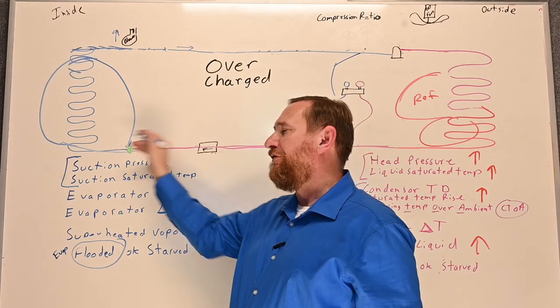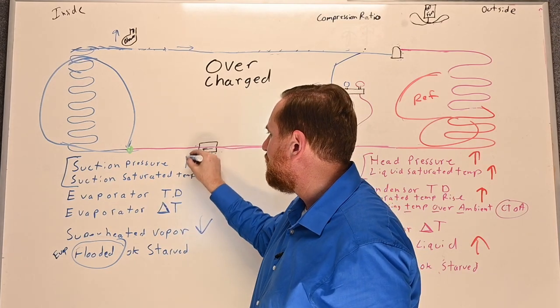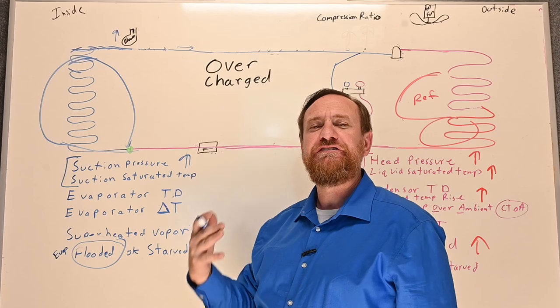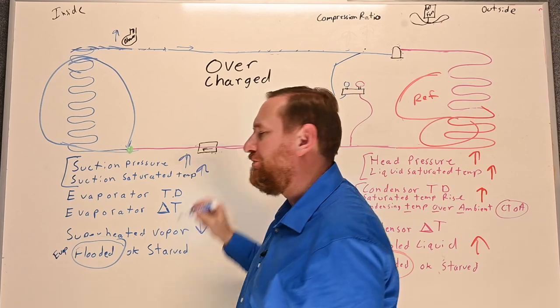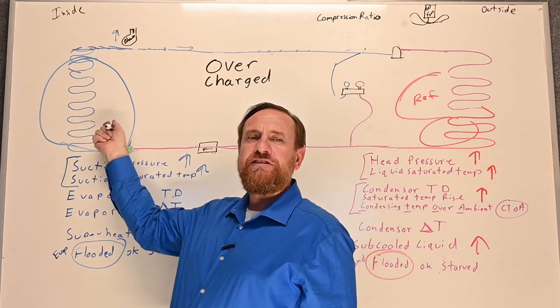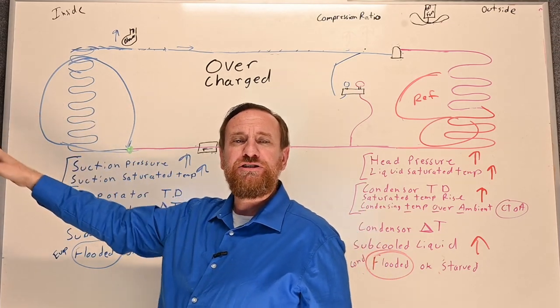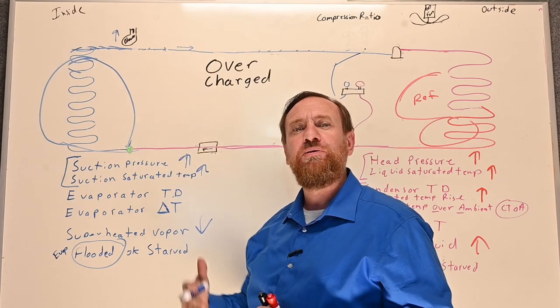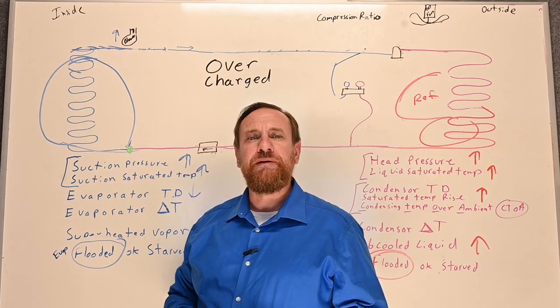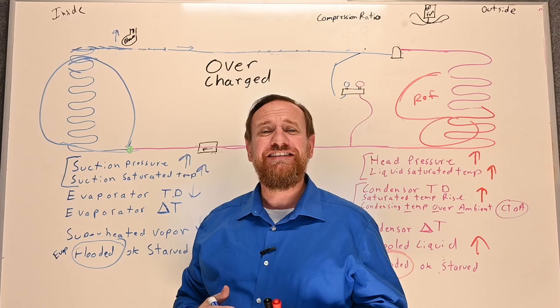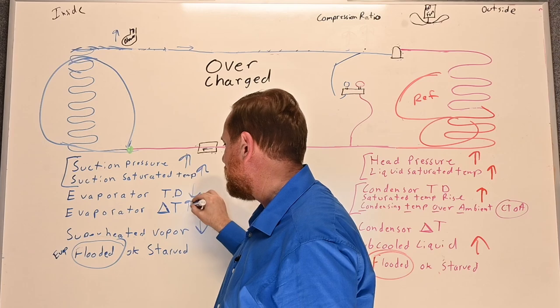On top of that, as I put more refrigerant in my evaporator coil, my suction pressure is also going to go up. And we know if our suction pressure goes up, our saturated temperature — the temperature of the refrigerant boiling — is tied to that, so our saturated temperature goes up as well. Now the air temperature is still the same, so the temperature difference between the refrigerant and the air is closer together, meaning our evaporator TD may drop. Our evaporator delta T — air in versus air out — will typically get farther apart, so that number goes up.